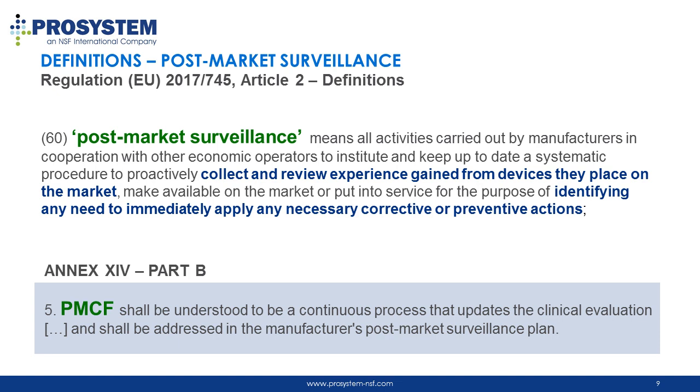To better understand the last part of the definition of clinical data, we need to go to the definition of post-market surveillance. Manufacturers are required to implement a post-market surveillance system to collect and review experience data from devices placed on the market. A post-market surveillance system should also include post-market clinical follow-up activities, PMCF, which is a continuous process to proactively collect clinical data. Therefore, the definition of clinical data in the regulation makes it clear that experience gained from devices on the market are a source of clinical evidence on safety and performance.